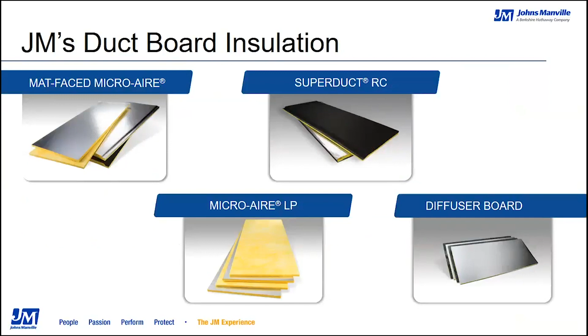Looking at them a little more in depth, you see the mat-faced Micro-Aire duct board on the left-hand side. It comes in 3 thicknesses. It has an FSK facing on the outside, providing that vapor barrier. The black mat is always on the airstream side of that product. It's really the workhorse product of the duct board portfolio, and the one we sell the most into the market. The next product is the SuperDuct RC product.